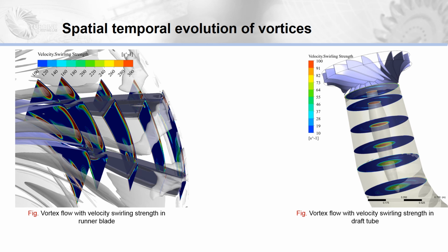The vortex rope downstream of the runner is very highly affected by the flow behavior in the runner, though the design condition indicating zero swirl at the outlet of the runner was modeled for the current numerical study. The high-intensity vortex was found to gradually grow up to 50% of the draft tube cone and then reduced before reaching the draft tube elbow.